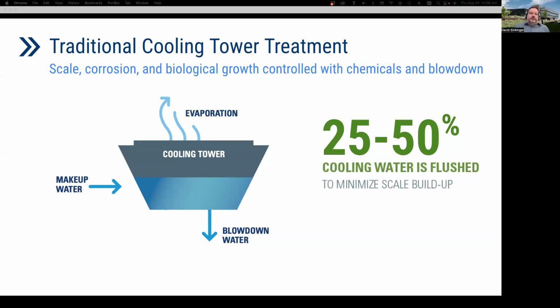The typical approach to control these issues is a combination of chemical treatment and blowdown. Blowdown is discharging water to the sewer from the bottom of the cooling tower basin, and that can be as much as half in some cases. The simple graphic here is showing a cooling tower's water inputs and outputs. So makeup water is introduced to dilute the remaining solids and replace water lost through evaporation and the blowdown process.